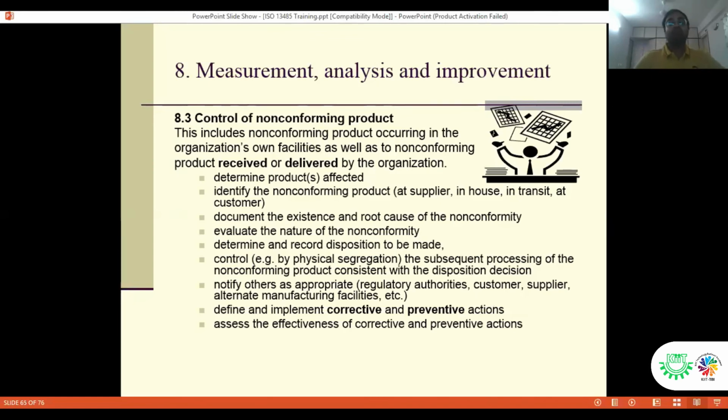At the time of manufacturing your devices, there are standards of rejection. So you have to have a clear system in place to bifurcate conforming and non-conforming devices. You have various tagging of your devices. Suppose a non-conforming device, you can tag it with a red color and a conforming device with a green color, so that the further movement of devices through the different stages of manufacturing becomes easy for the employees.